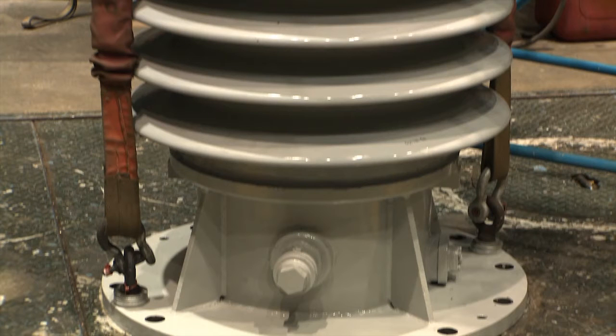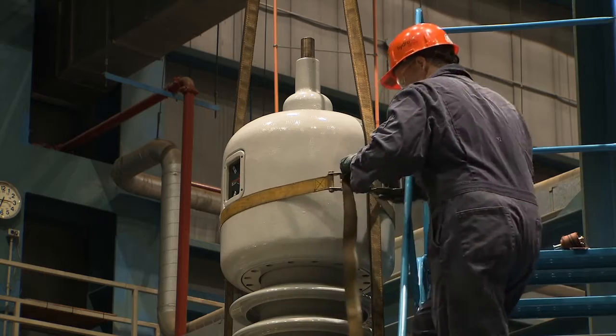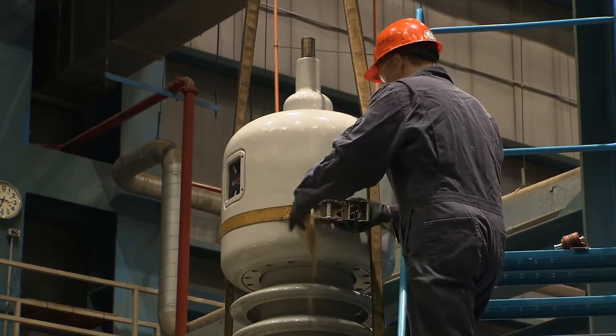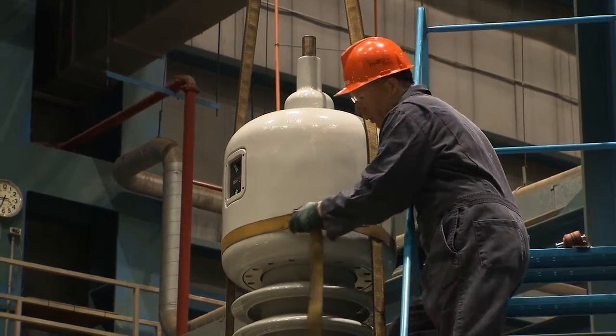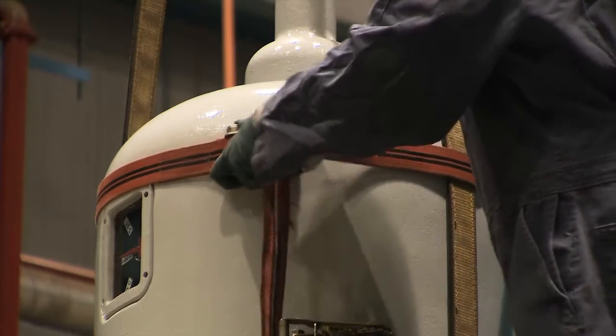The 2 slings attached to the hoist crane are choked onto 2 separate shackles, which are locked onto the eye bolts. Wrap 2 tightening slings around the lifting slings on the upper half of the oil reservoir. This secures the bushing from falling when the crane is lifting it.